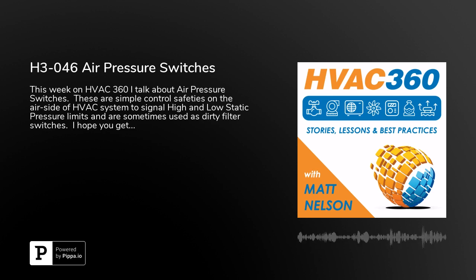A lot of times, if you take a look at the unit itself, the air pressure switch, the high limit, low limit, you're going to find one of either the highs or the lows disconnected. It's going to be open to the atmosphere. And that's going to be your reference pressure to make sure that you get the right measurement. So similar to what you'd find in the diaphragm type.